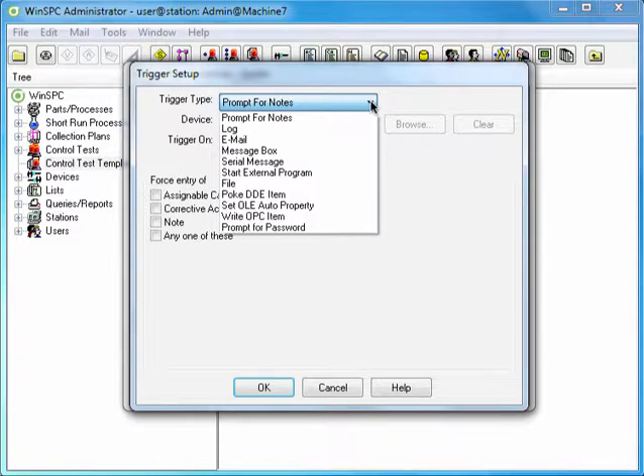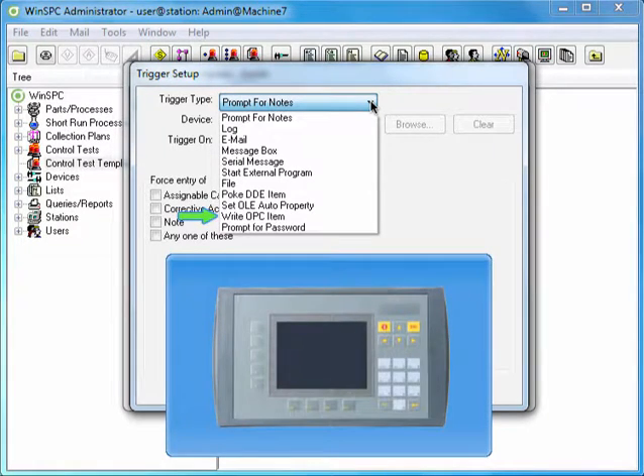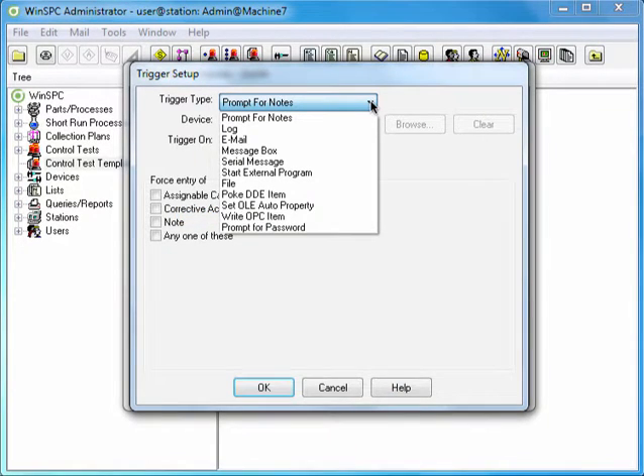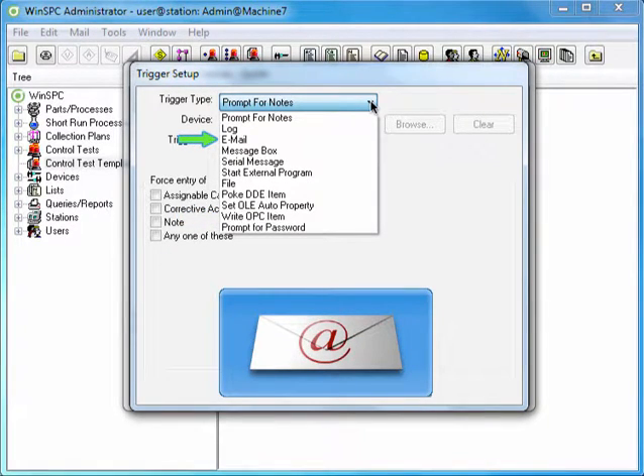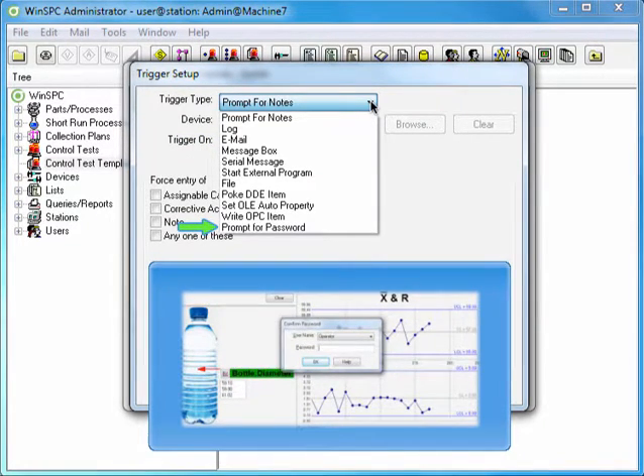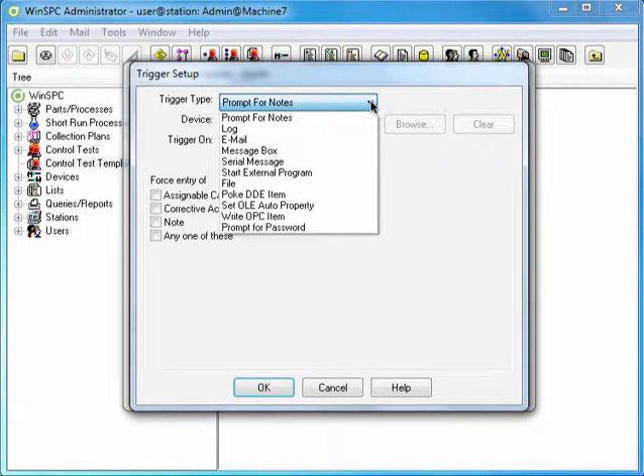These are the triggers available to you. Some initiate action without human involvement, while others alert shop floor personnel so they can initiate action. The Write OPC Item trigger, for example, can automatically send a set point or calculated value to a PLC that uses OPC technology, enabling the PLC to self-correct a setting such as temperature. You can email supervisors or other personnel when a test is violated, interrupt data collection and prompt for a supervisory password, or trigger a variety of other actions. If you would like an explanation of a trigger in this list, mouse over that trigger now.